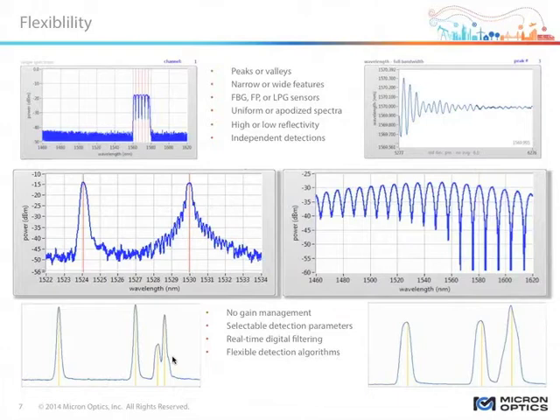And our ability to use that information or calibrate that information is compromised as we have to manage a changing number of peaks. Perhaps another scenario would be this is a high quality FBG sensor that's been stretched to 3 or 5% strain, and it's moved 30,000 picometers. That information is extremely valuable. We want to know if it's moved 10,000, 20,000, 30,000 picometers, but perhaps the precision of 1 picometer is of less import at that point than is knowing within 10 picometers exactly where that sensor is and that we reliably detect that 1 peak.